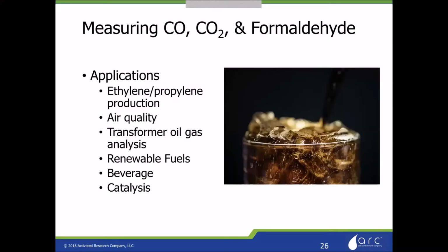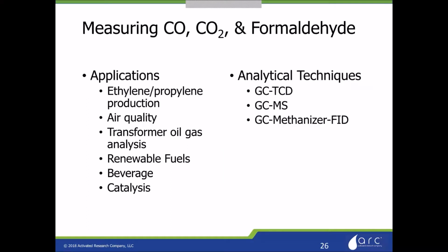So some of the applications where this is useful: CO and CO2 have been important in ethylene and propylene production, specifically because carbon monoxide poisons catalysts at very low levels. Air quality, of course, greenhouse gases, transformer oil gas analysis is another one where levels of CO and CO2 can indicate failures in the transformer oil or the transformer itself. Renewable fuels, beverage analysis, and catalysis. And typically, TCD has been used, although it has a very high limit of detection.